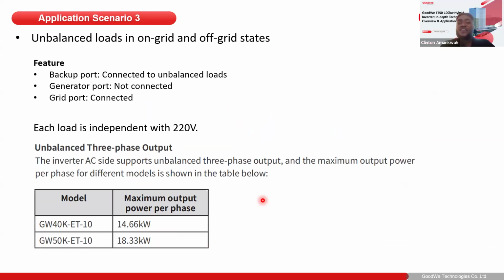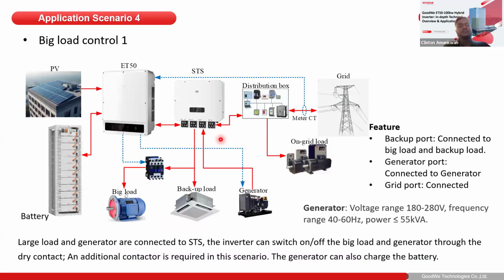So let's say one phase has a demand of 5 kilowatts, the other phase has a demand of 3 kilowatts, and then the other phase has a demand of, let's say, 16 or 18 kilowatts. So far as the maximum demand per phase is not more than the maximum the inverter can give, which is 18.33 kilowatts for the 50 kilowatt inverter, your inverter can still deliver uninterrupted power supply to this unbalanced load in on-grid and off-grid states, because each of the loads is independent with a single-phase voltage. This gives you huge flexibility and huge assurance of system performance.